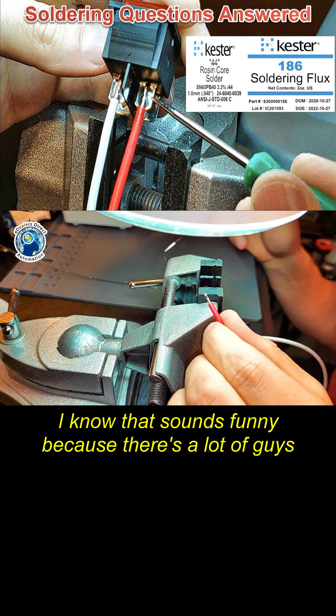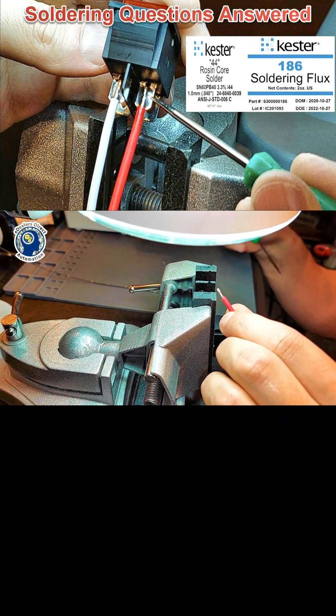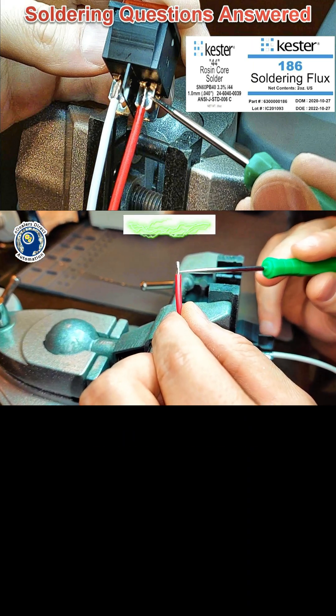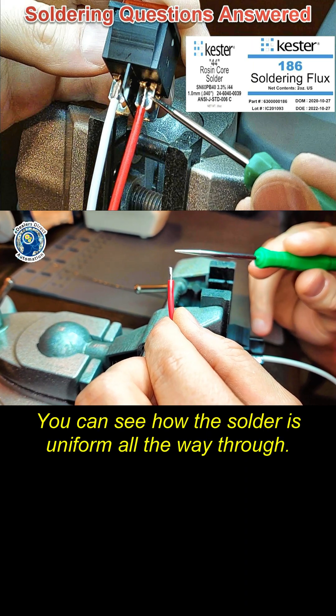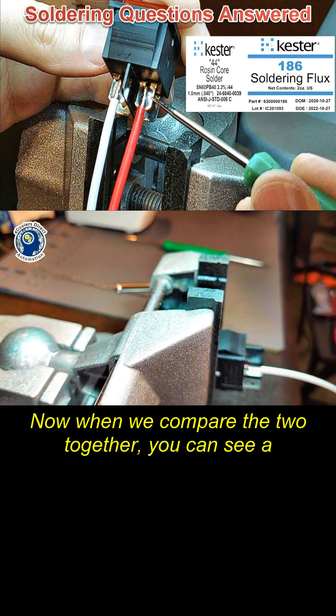There are a lot of guys online posting videos saying 'I just tinned it' — but that's not properly tinned. Let me show you exactly what I mean. Here's a properly tinned connection — you can see how full the lead is, how the solder is uniform all the way through. This is a perfect bond, welding all the conductors together.